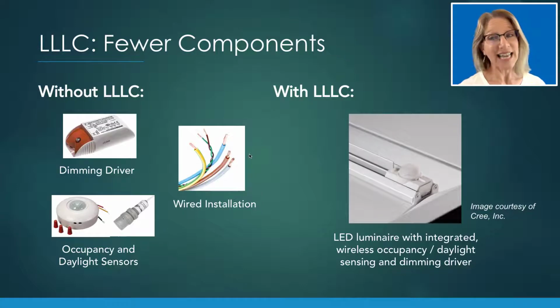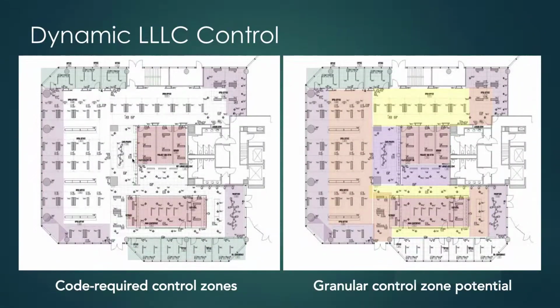Here's a comparison of legacy lighting control and Luminaire level lighting controls. Instead of installing and wiring a bunch of separate components, Luminaire level lighting controls can speed up installation, can shorten construction schedules, and it can reduce errors in the field. Here's an example of a code-required control zones within an office space. With Luminaire level lighting controls, additional zoning and layering of control schemes can improve energy savings and help tailor specific lighting needs by task, area, or even by personal preference. Future changes to lighting that would normally require pulling wire and balancing circuits are simplified by simple reprogrammable individual luminaire assignment.